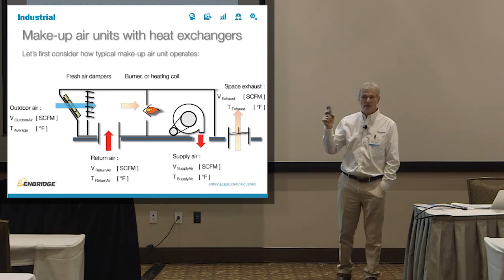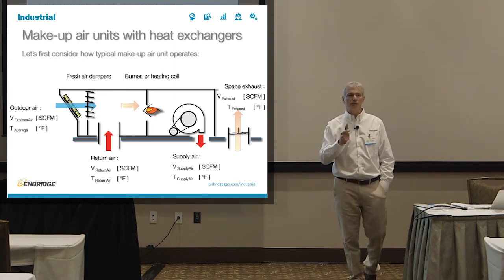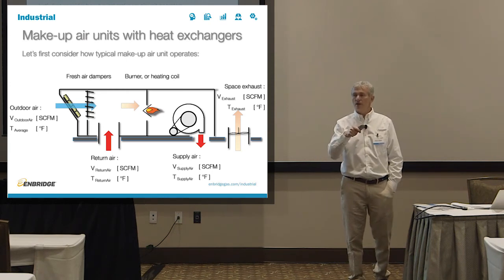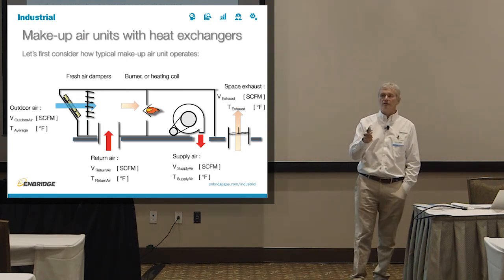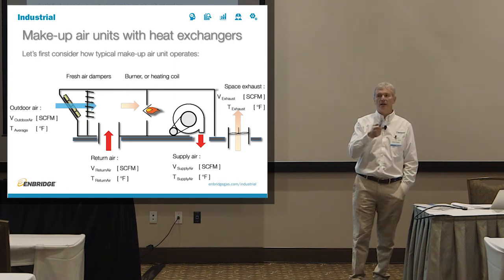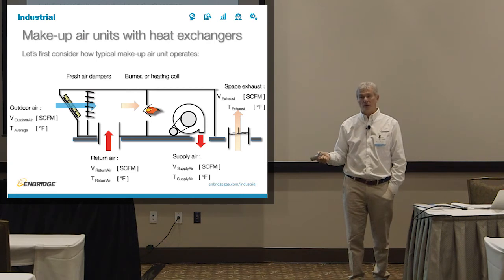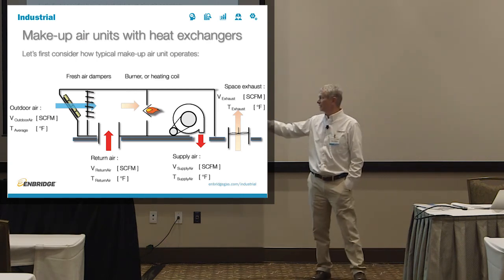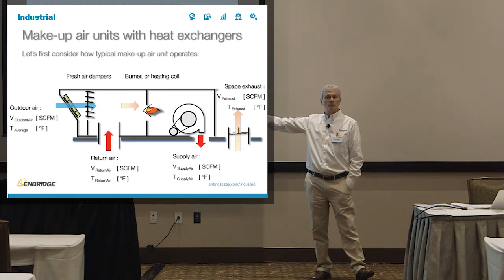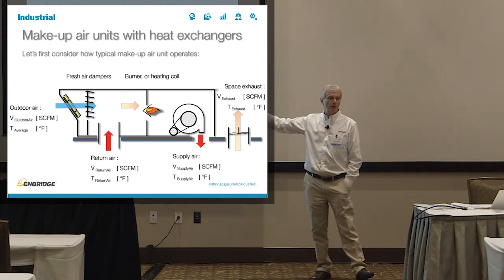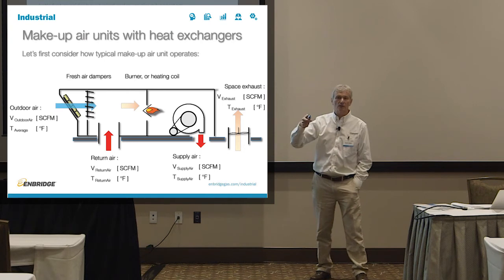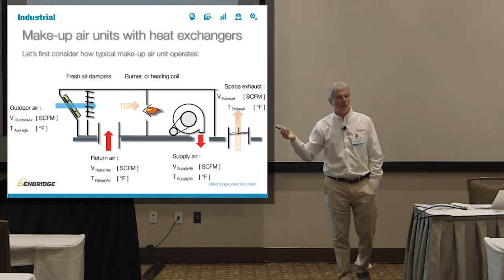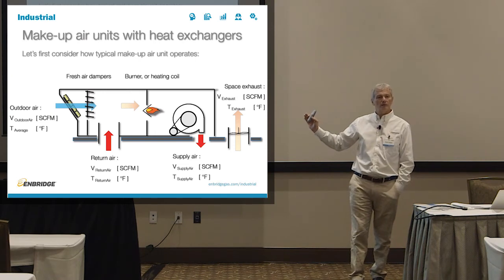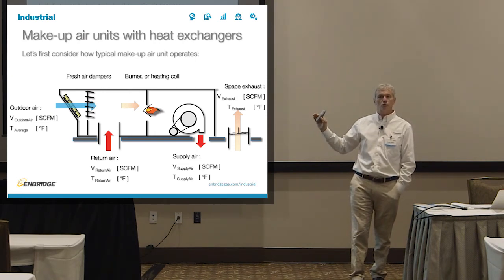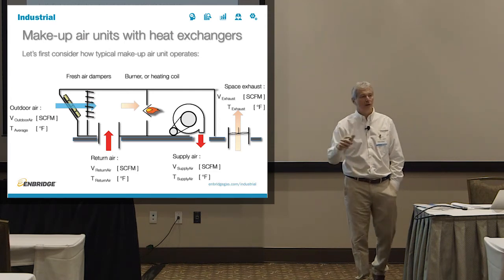Because it's a very common thing that people call us and say, I have 50,000 CFM of makeup air coming in, and I want to save all of that. And when you really do the analysis, there is no way they can use 50,000 CFM of air and heat it, based on the consumption profile that they have. And in 9 out of 10 cases, what ends up happening is they have some return air they didn't take into account. Return air you can think of as almost a freebie. You only have to heat it up by 1 or 2 degrees. Most of you are not concerned with the humidity levels, so it's not air conditioning. So you'll only lose 1 or 2 degrees at max, and that will not generate enough energy consumption for it to be worthwhile recovering.